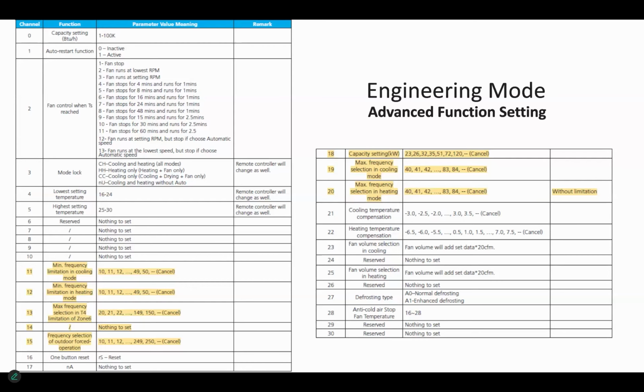what it does is it takes the defrost termination temperature and increases it to, I think, 25 degrees C. Which is about 77. What's it come out of the box for? 16 C, which is about 60. So we're coming out of the box with a defrost term of 60. Right. Wow.